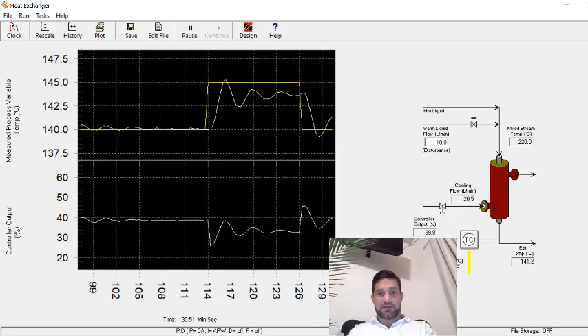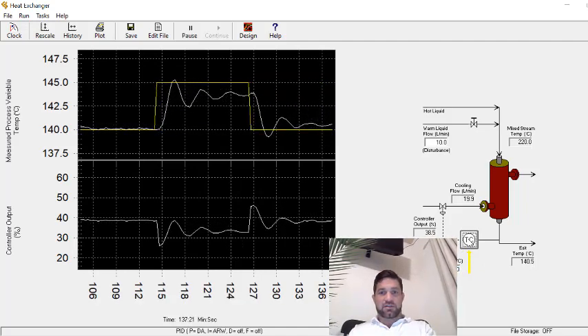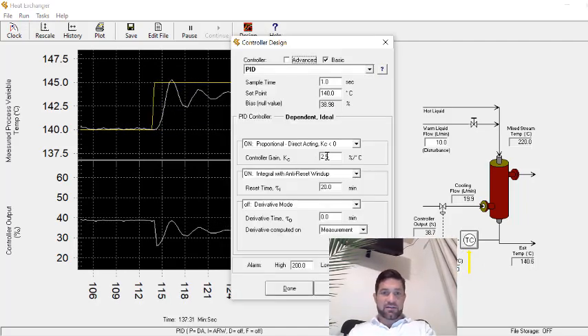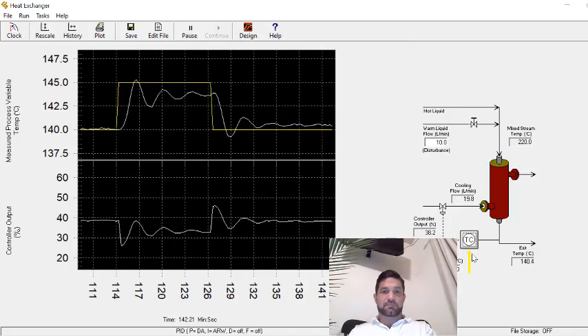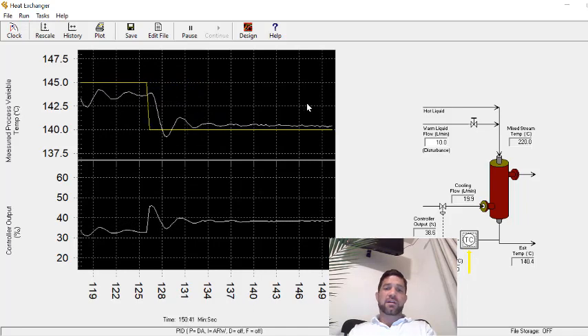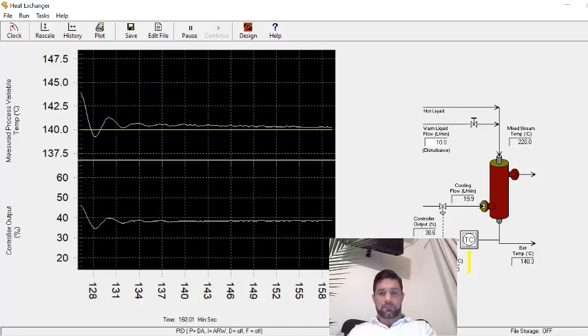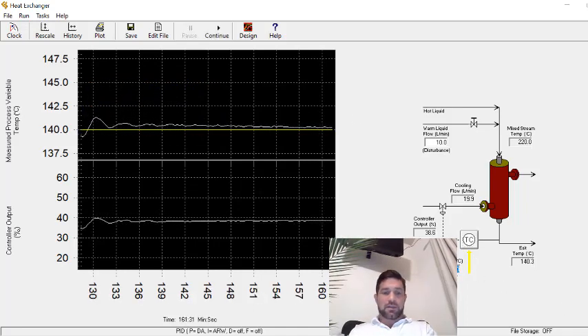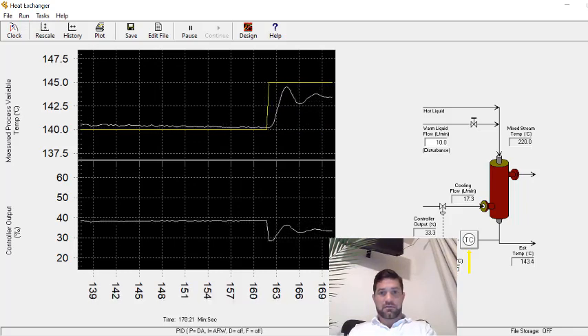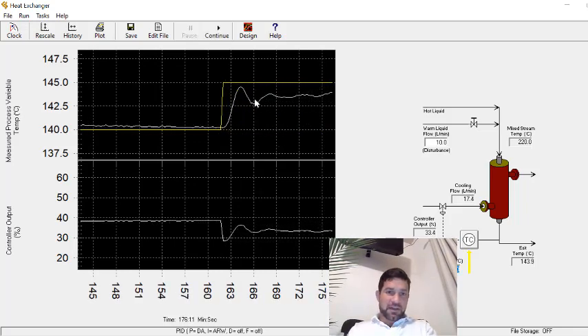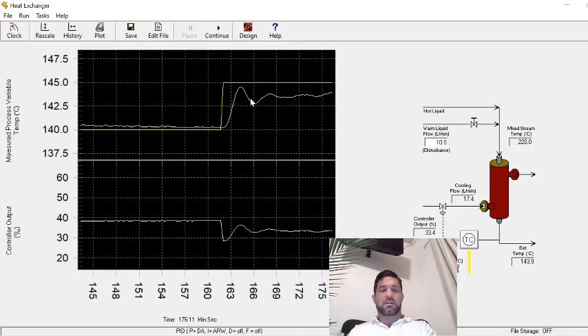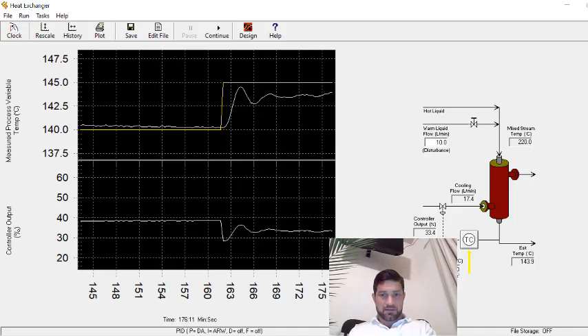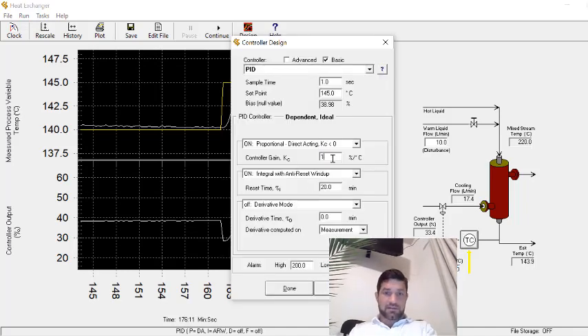So gain is still too large. Let me step this back down. Still too large coming down. Maybe we'll put this at 2 and see how this looks. We want to let this settle out, then apply our step change to 145. We see our first peak to valley. It's a little bit more than 16%.